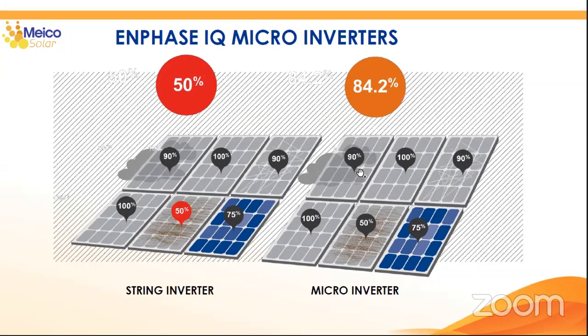So in this case, you're not having the 50% of the generation because each microinverter has its own MPPT and it's set to the parameters of that specific module. And then you're gonna have 84.2% of the efficiency or the power generation because it's the average of the power generation you're gonna have for each module. So that's the benefit of the microinverters. You're gonna have better and more power generation in the projects where you're gonna find these types of conditions. Those projects are normally residential or commercial. When you have trees, you have wires, you have different orientations in the modules, shades, whatever you can find in a residential and small commercial, that's the project you will find better for ENPHASE because the difference in power generation is gonna be really, really high.